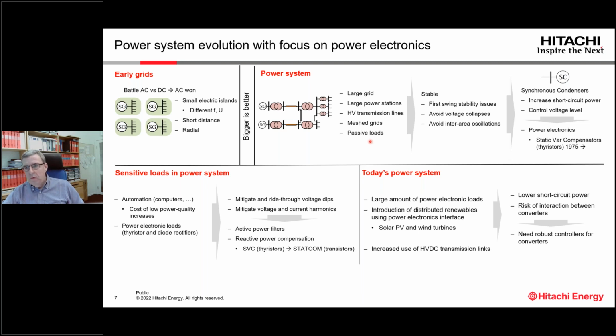One way to avoid this, part of the solution, has been to use synchronous condensers. With synchronous condensers we can increase the short circuit power and control the voltage level. However, synchronous condensers have some disadvantages, so in the 70s we started to replace synchronous condensers with static VAR compensators using thyristors.